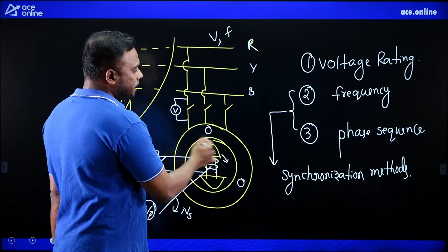So if you want to change the phase sequence of the alternator, what do we have to do? Simply reverse the direction of rotation. It was rotating clockwise previously, and then the sequence is RBY, so the phase sequence is not matching. Then reverse the direction of rotation of this turbine or rotor, so that the sequence will change automatically. So phase sequence can be adjusted by interchanging the direction of rotation of the rotor. Frequency can be adjusted by changing the speed of the turbine.